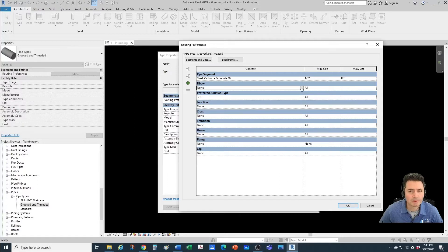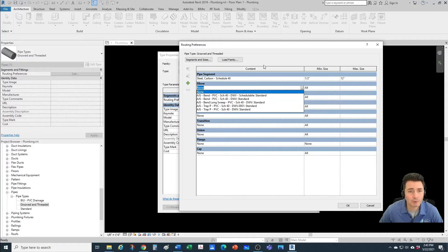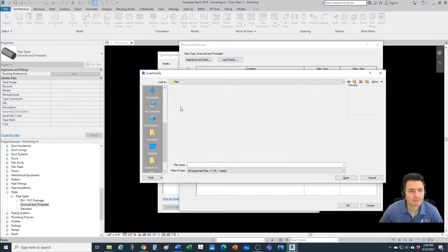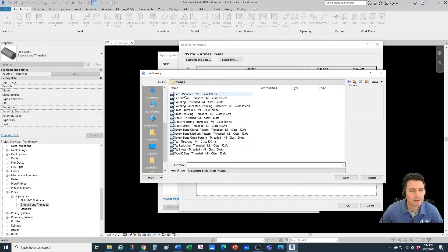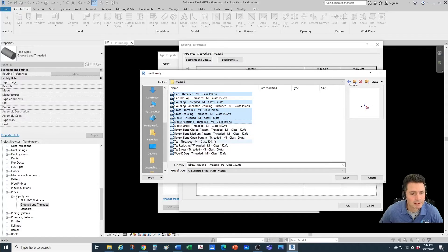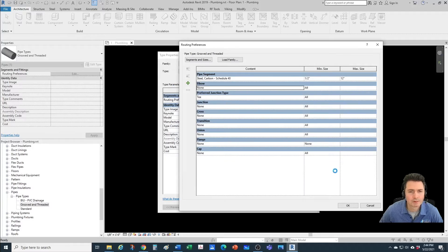Before we start selecting our fittings, since we don't have them loaded into the project yet, we have to go into Load Families. We'll go into Pipe Fittings, then Malleable Iron, then Class 150 Threaded, and select a bunch at once: a threaded cap, a coupling, a cross, a cross reducing, an elbow, an elbow reducing.